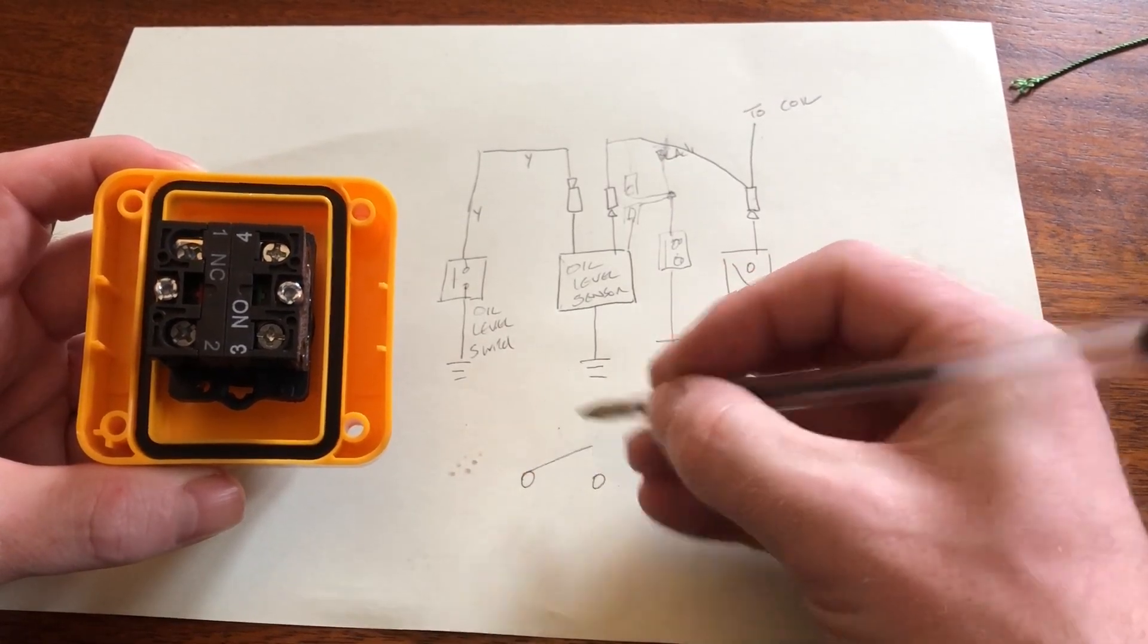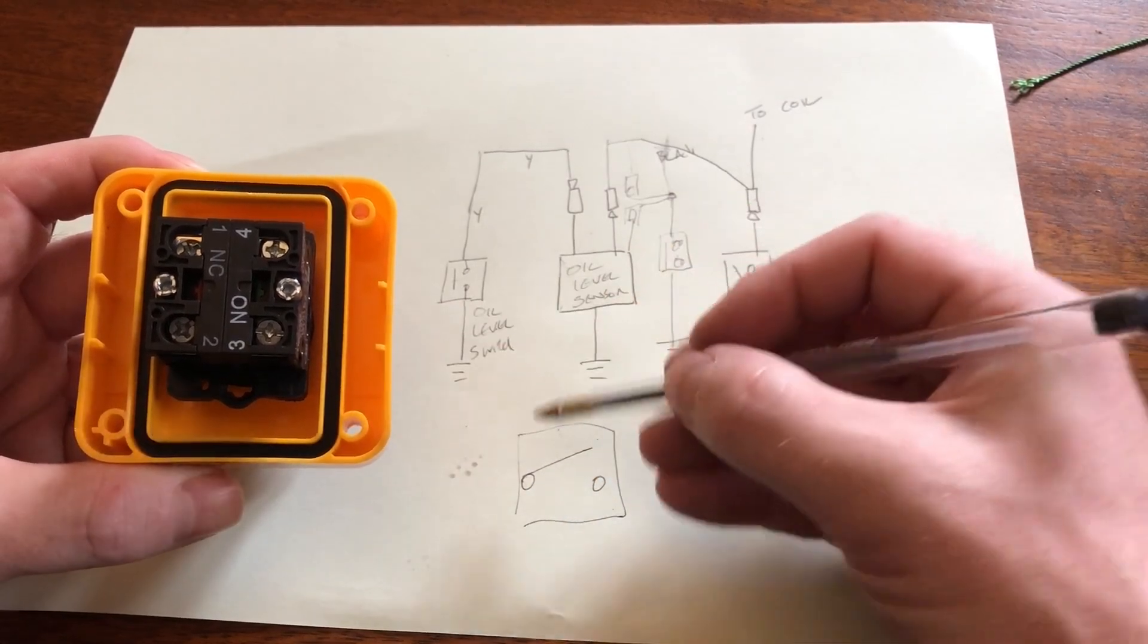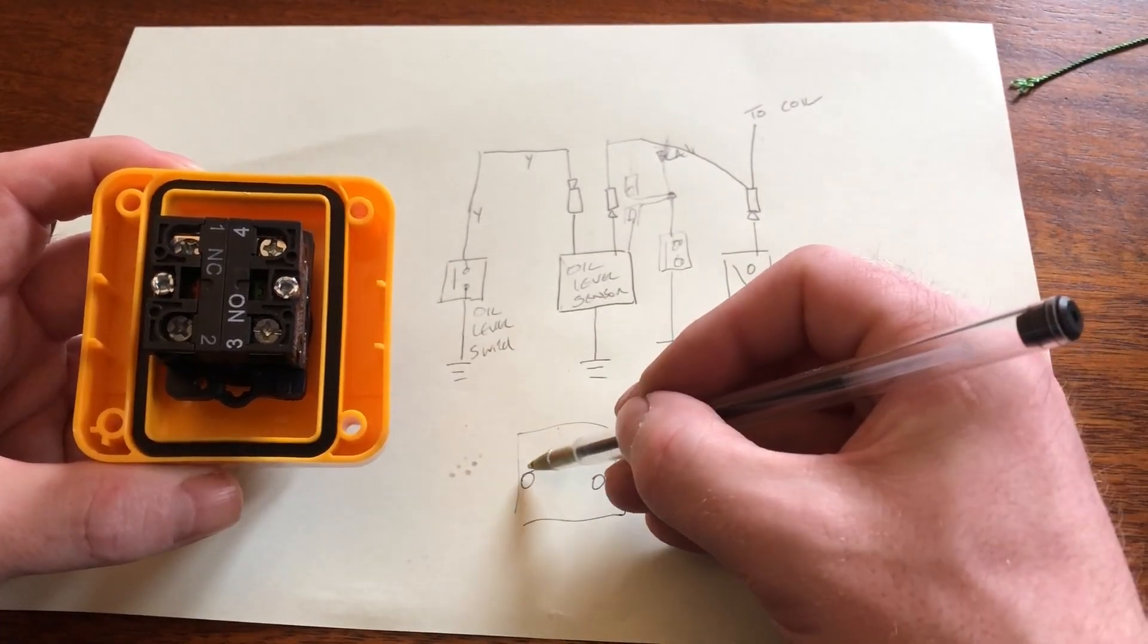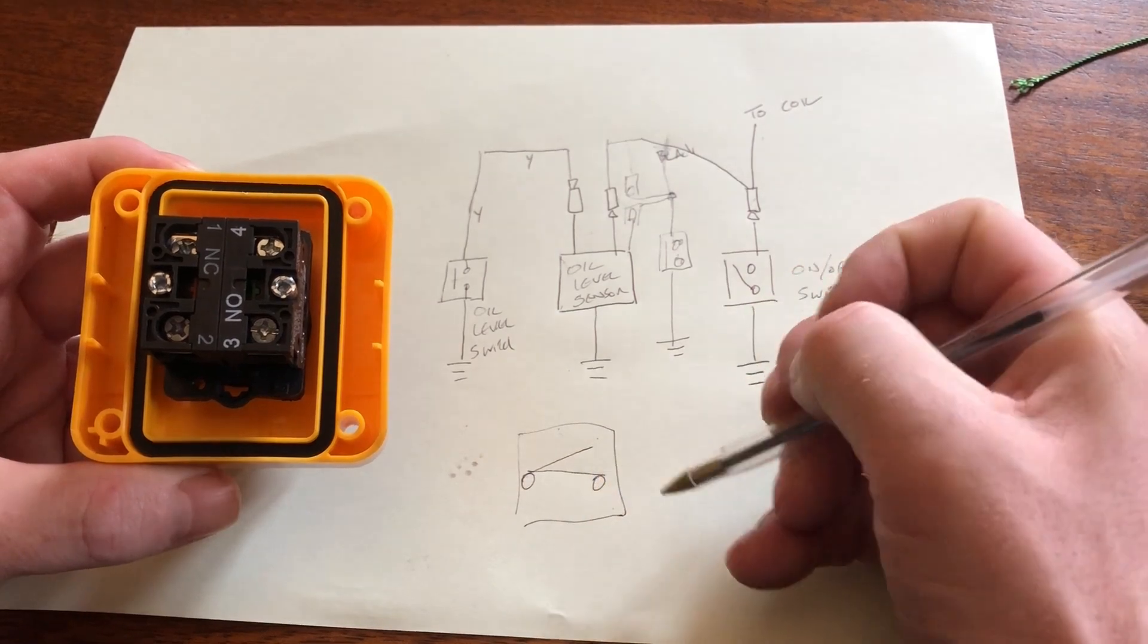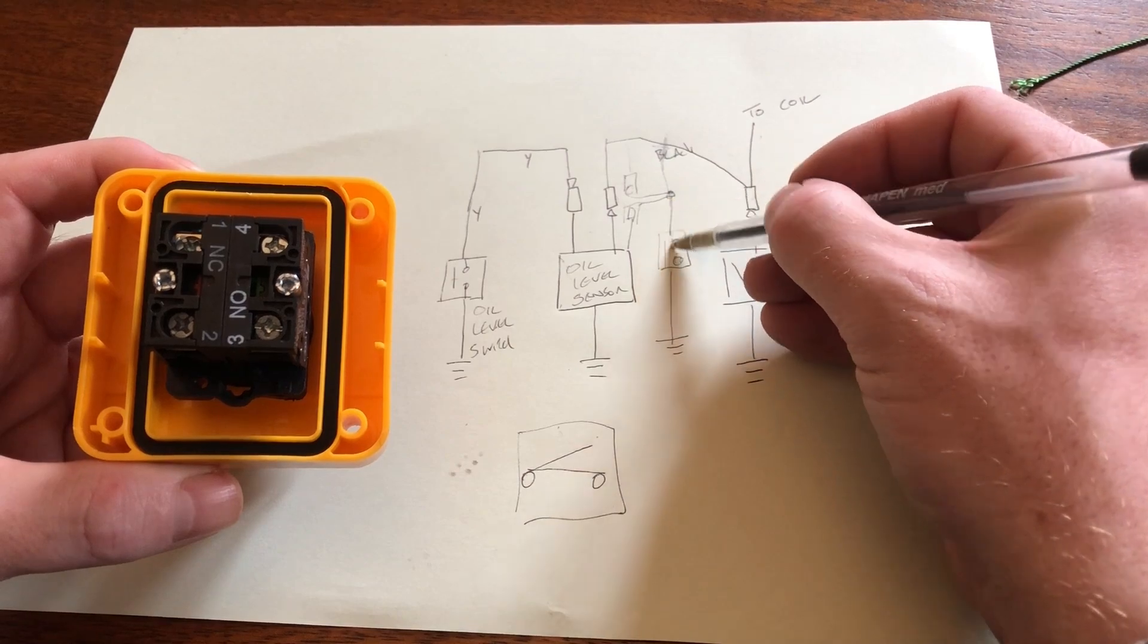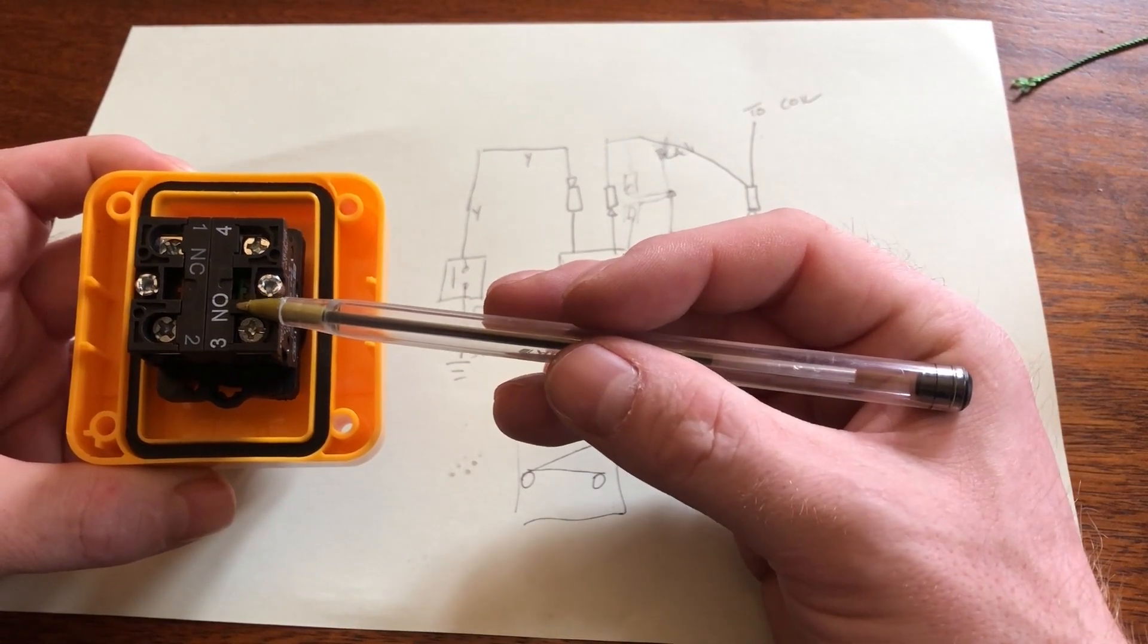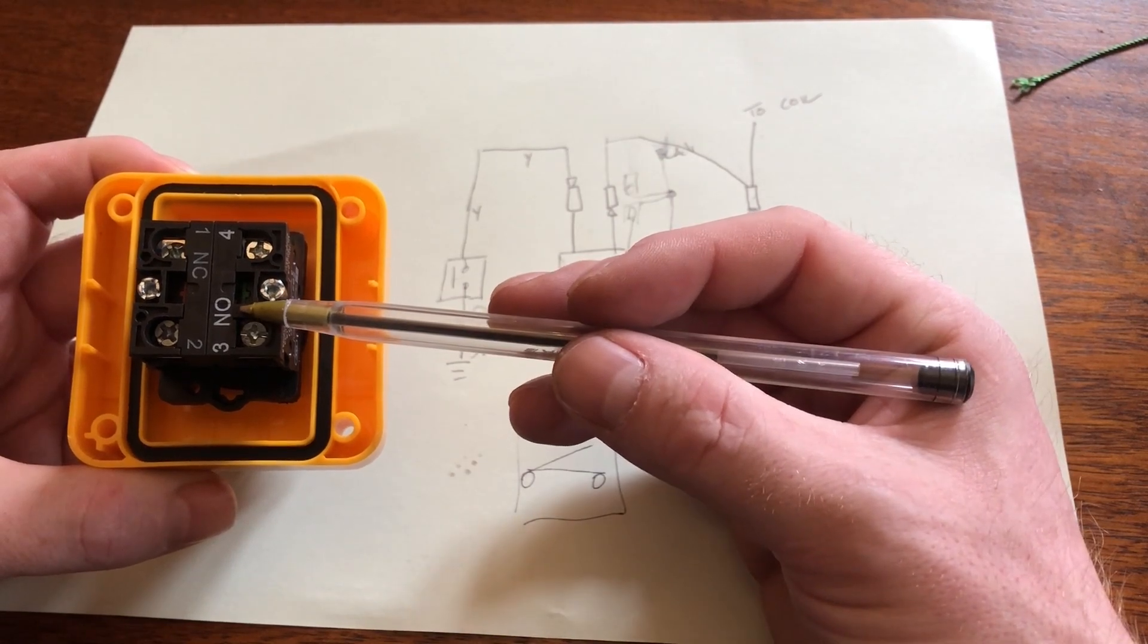Basically inside, that normally open switch is like that - normally open, so it isn't touching. When you hit the emergency stop, that then closes and touches because you want that configuration. So when you hit it, that closes and puts that coil down to earth. Make sure when you're buying an emergency stop, get a normally open emergency stop.